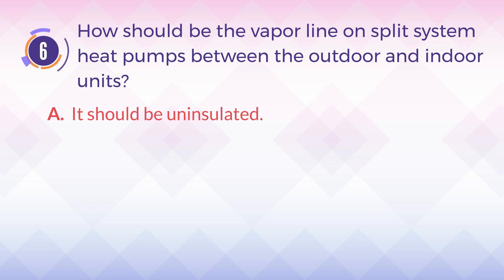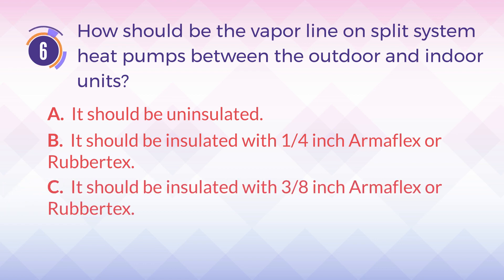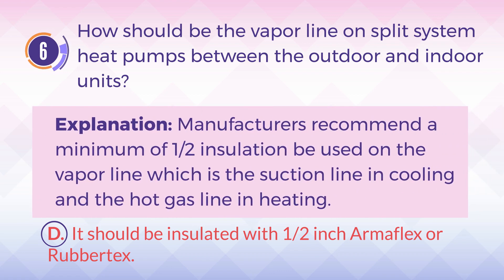A. It should be uninsulated. B. It should be insulated with 1/4 inch Armaflex or RubberTex. C. It should be insulated with 3/8 inch Armaflex or RubberTex. D. It should be insulated with 1/2 inch Armaflex or RubberTex. The answer is D. Explanation: Manufacturers recommend a minimum of half-inch insulation on the vapor line, which is the suction line in cooling and the hot gas line in heating.